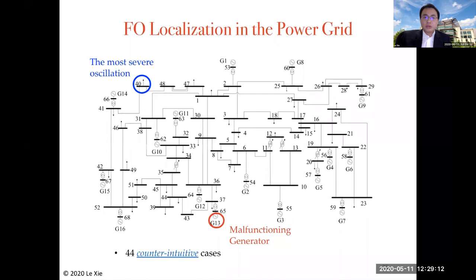So we tested it out using both a synthetic and a real-world example. This is what a synthetic example looks like. It turns out that bus 40 shows the most severe oscillation, whereas the troublemaker is caused by the malfunctioning generator at G13, which is completely far, on the opposite end of the system. So these are very counterintuitive problems.